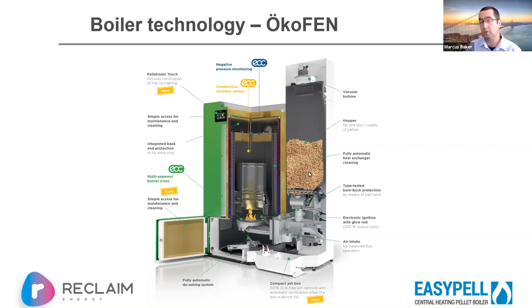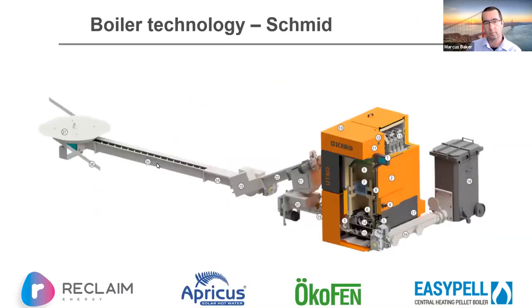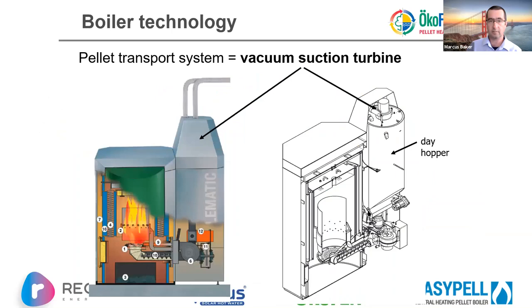It's called vacuum but it's actually a blower. The day hopper may be filled multiple times in a commercial context — for Ökofen that's about 65 kilos, for some others 100 to 120 kilos. These aren't huge volumes. The day hopper then has a feed mechanism into the boiler — in some cases an augering system with an agitator that moves around to ensure pellets fall down correctly.